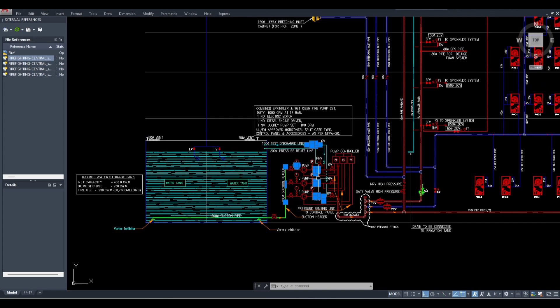Okay, see these things, if you'll check this, how many times do you have to do it? One time, right? In a project, this pump room comes one time. So if you do it correctly one time, maybe it can take one day. Now you are completely satisfied that my fire pump rooms are systematically correct. So again, I don't have to do the rework on this system, right? So that's how you check the system confidently if you are working like a coordinator.